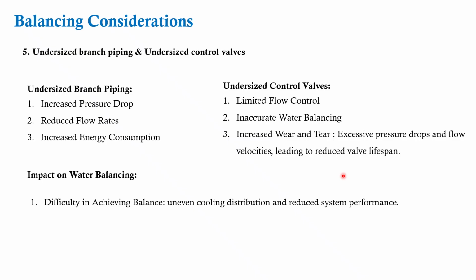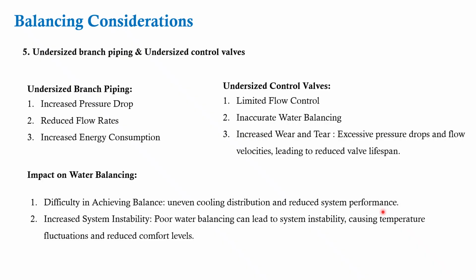It's going to be difficult to achieve water balancing. So uneven cooling distribution is going to be there in terms of the performance of the HVAC system. The second, it's going to increase system instability. Poor balancing is going to lead to poor performance in maintaining temperature, with fluctuations, and ultimately is going to add more energy consumption at the system level.